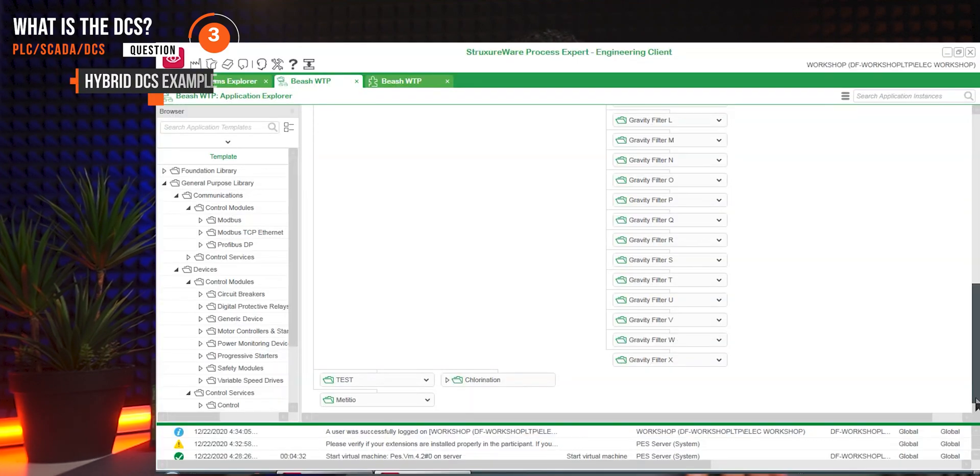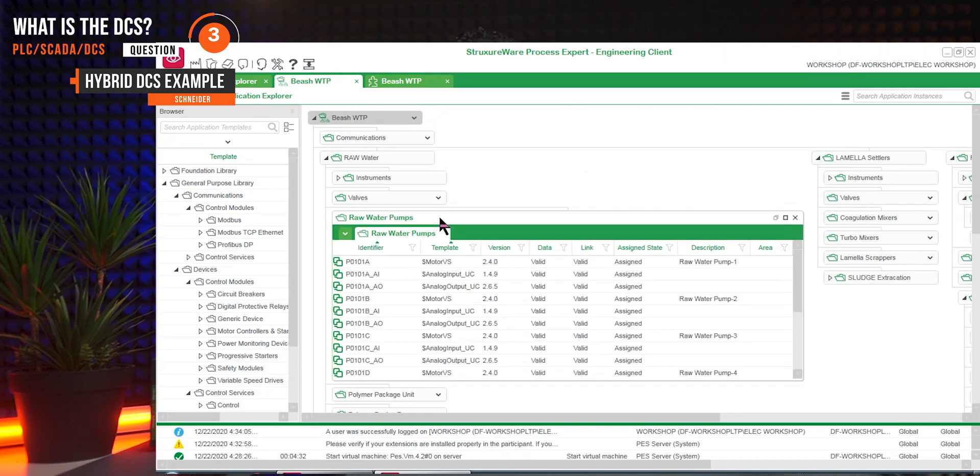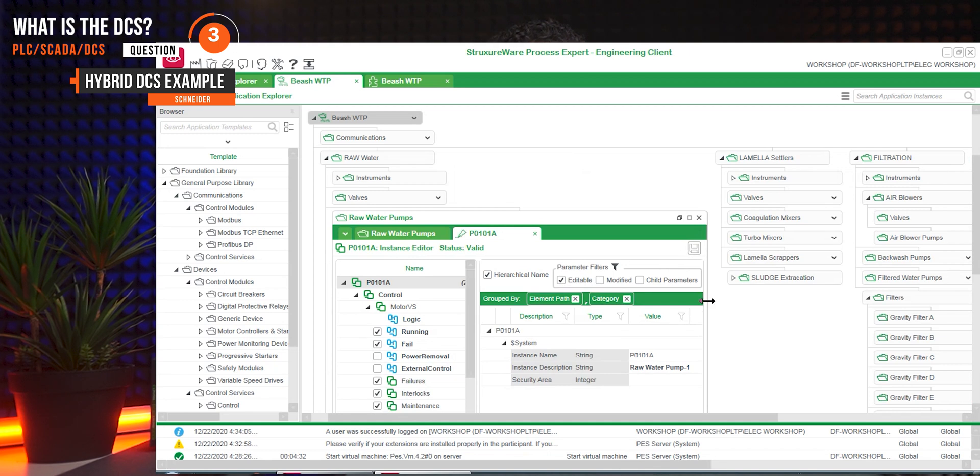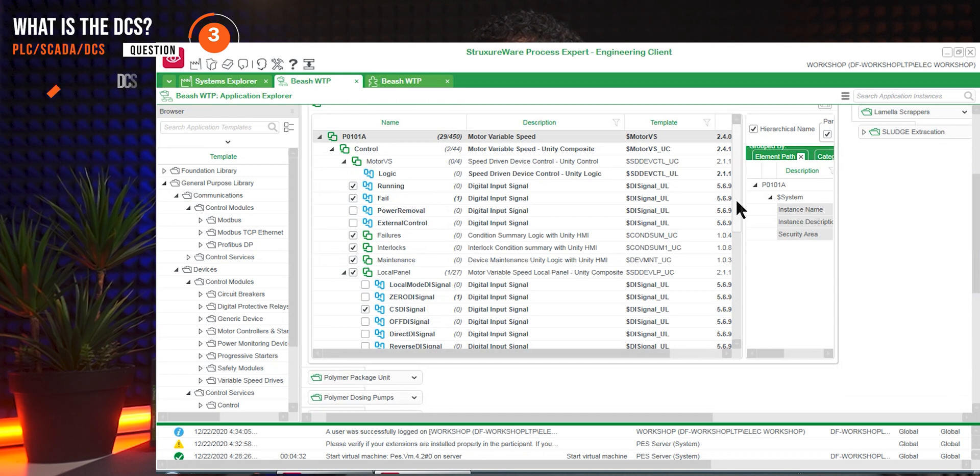In a SCADA system, you create a motor block in the PLC software and then the faceplate in the SCADA software, and then connect them using the suitable driver or OPC. In the DCS application generator, you define the motor equipment in the DCS, and the DCS takes the role of generating the motor block in the PLC software and the motor faceplate in the SCADA — connecting them including alarms and trends — through simple configuration checkboxes. This is the DCS link, which is the major difference: PLC software and SCADA software are linked together, and any modification in the DCS layer will be implemented directly and consistently.